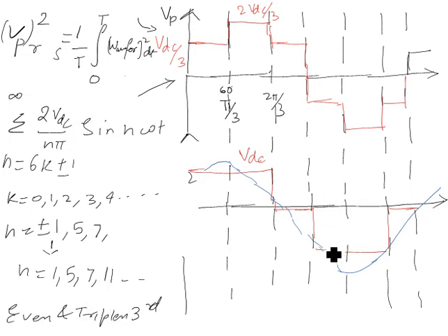Whereas this waveform, if you see this waveform, n contains 1, 3, 5. So the third harmonic is there here, and that is one of the issues. Triplen harmonics means you will go for the zero sequence component. For this waveform, you don't have that zero sequence. That is the circulating current that will be rotating in your star winding or delta winding. The delta winding will have this thing.